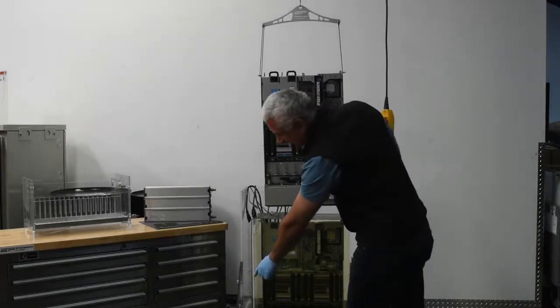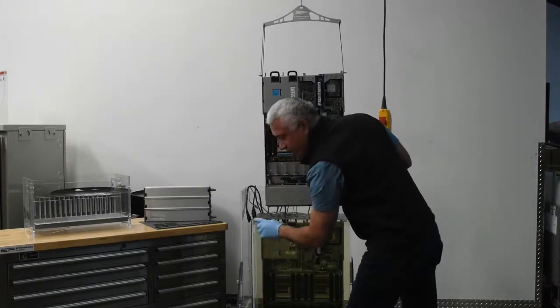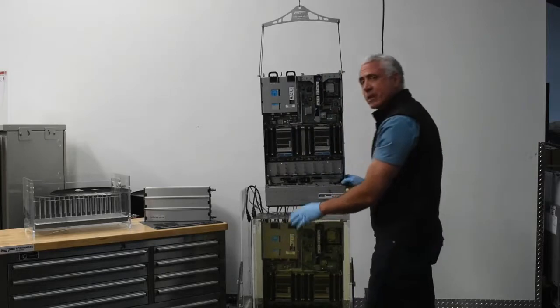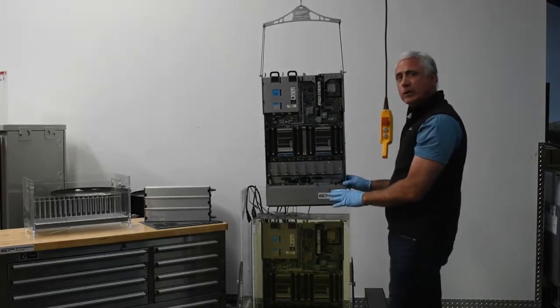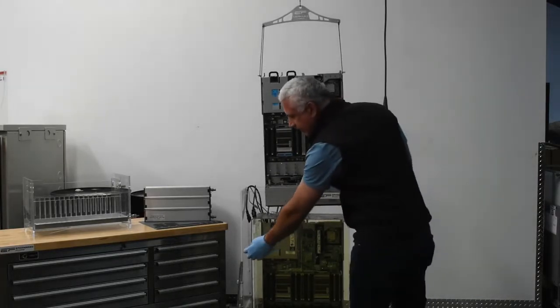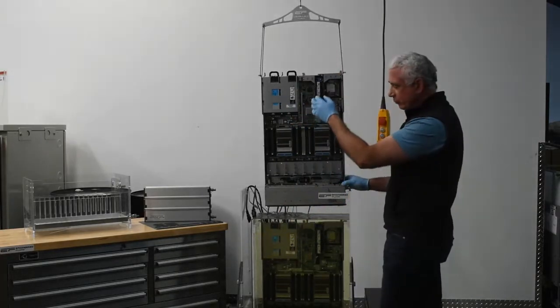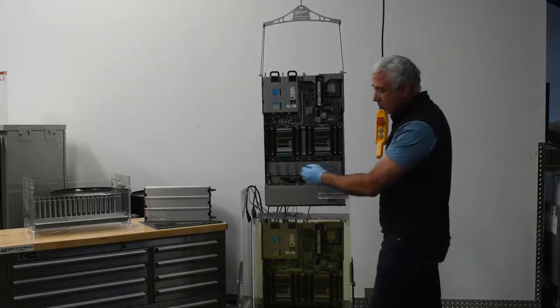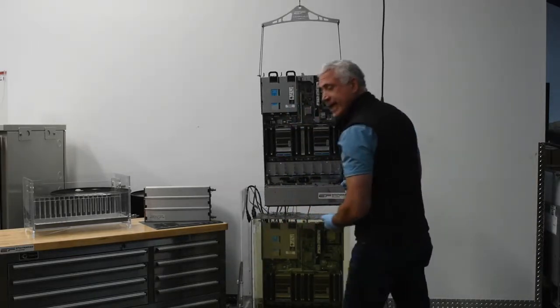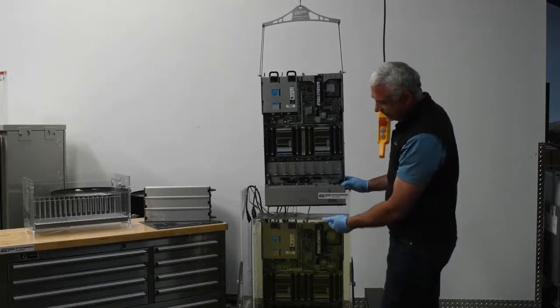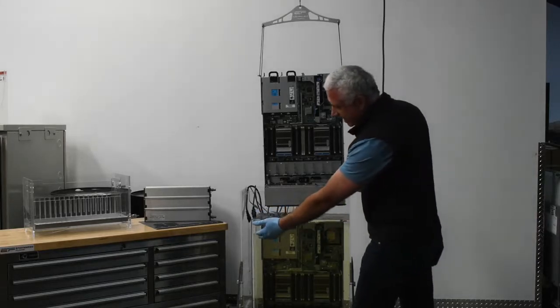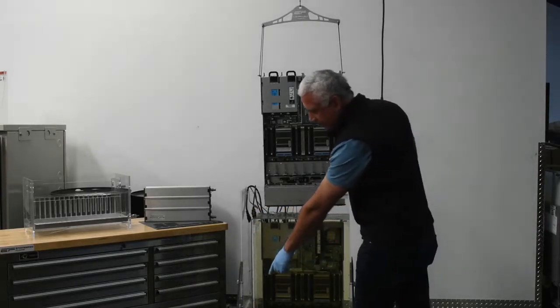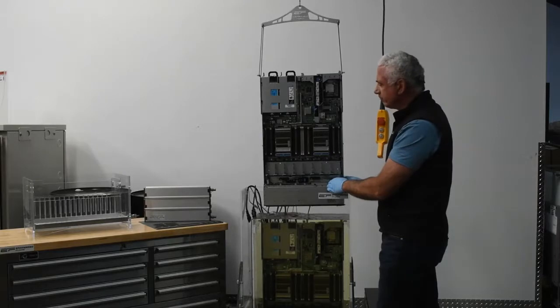You'll notice that on the tank design you can see that the level here has dropped considerably. That's really important in tank design to make sure that you have enough displacement area so that as we reinsert this server we don't overfill the tank. And you can see that the tank is continuing to operate just fine because we do have enough extra fluid.